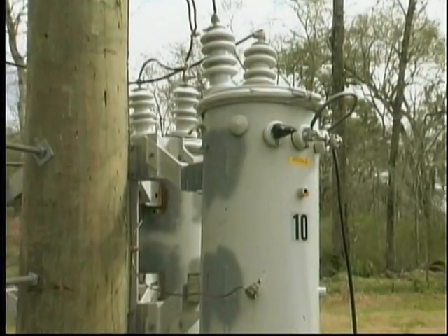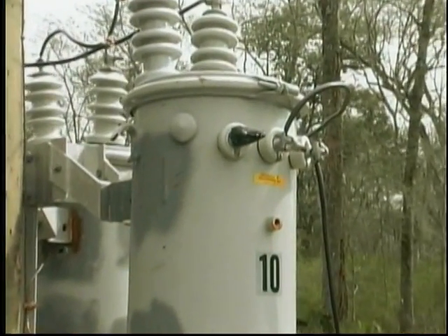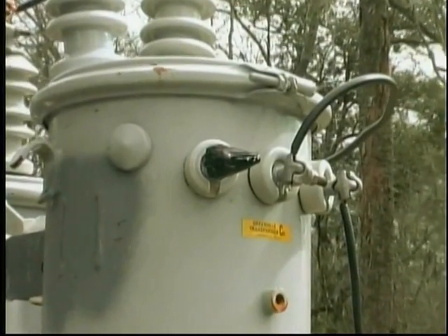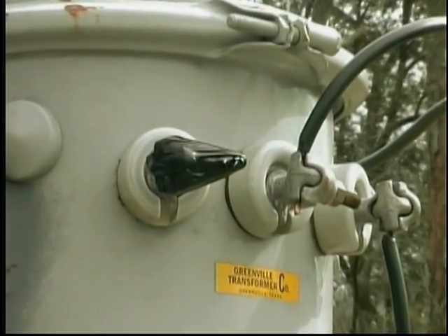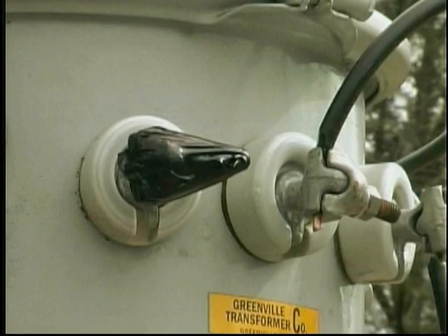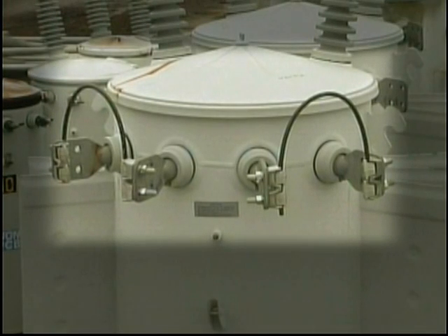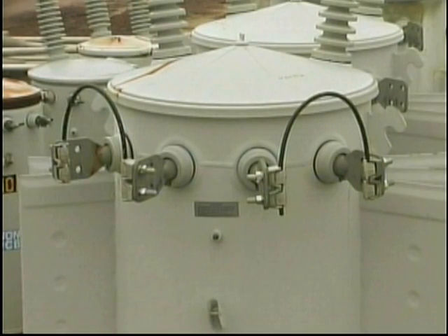Companies generally tape or tag the X3 bushing in some way to alert their workers not to make any electrical connections to the X3 bushing. If a unit with 4 secondary bushings is used, the connections are made outside the transformer by jumpering together the bushings connected to the corresponding end of the windings. The result is still the same. Only 2 connections can be made to the secondary winding.